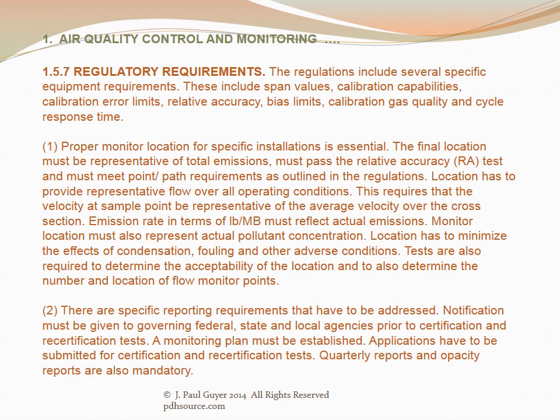Location has to provide representative flow over all operating conditions, requiring that the velocity at the sample point be representative of the average velocity over the cross section. Emission rate in terms of pounds per million BTU must reflect actual emissions. Monitor location must also represent actual pollutant concentration and must minimize the effect of condensation, fouling, and other adverse conditions. Tests are also required to determine the acceptability of the location and the number and location of flow monitor points.